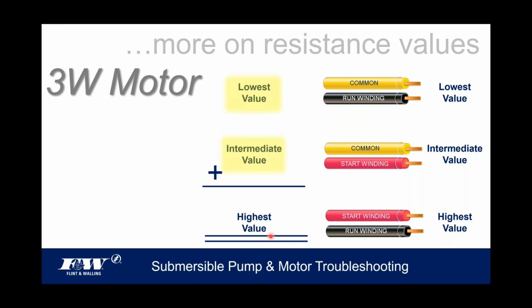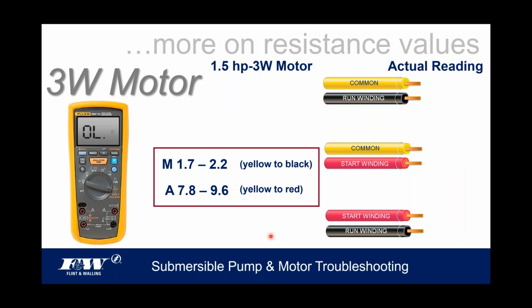You take the lowest value, add it to the intermediate value, and that ought to give you some idea as to what that high value should be. So it's pretty much a basic math equation here. And I'm not saying you have to be absolutely spot on. In other words, if the low value was 2 and the intermediate value was 8, meaning the highest value would be 10, that's what we just said. Well, what if it's 10.1? Hey, it makes sense to me. Close enough. So it just needs to make sense.